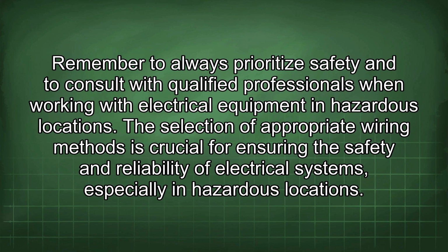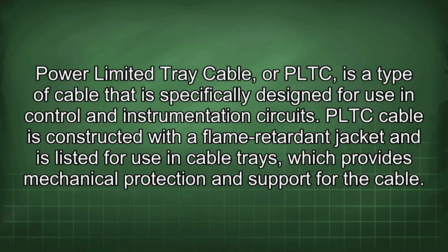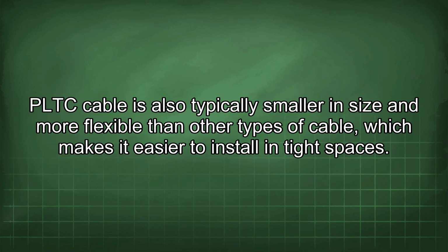hazardous locations. The selection of appropriate wiring methods is crucial for ensuring the safety and reliability of electrical systems, especially in hazardous locations. Power limited tray cable, or PLTC, is a type of cable that is specifically designed for use in control and instrumentation circuits. PLTC cable is constructed with a flame retardant jacket and is listed for use in cable trays, which provides mechanical protection and support for the cable. PLTC cable is also typically smaller in size and more flexible than other types of cable, which makes it easier to install in tight spaces.